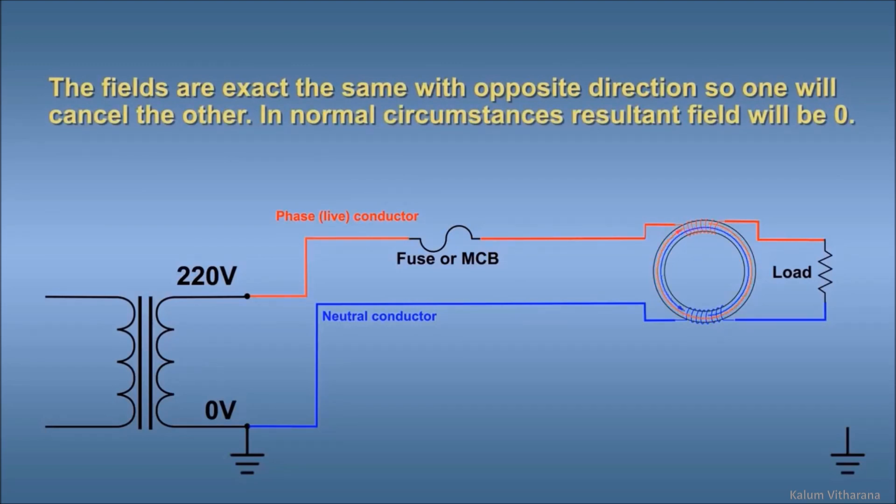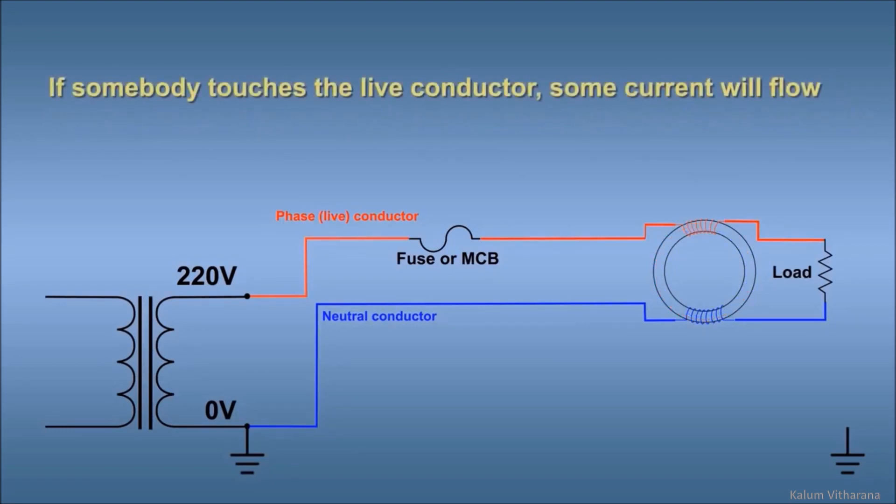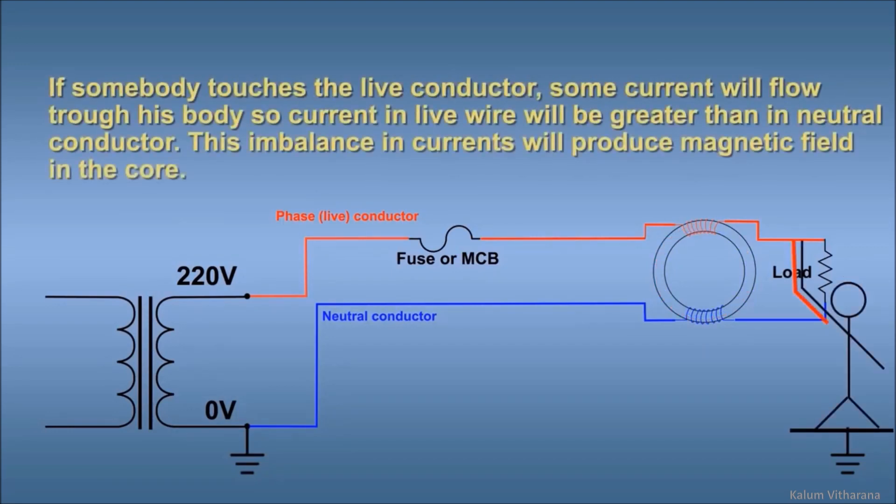The magnetic fields are exactly the same with opposite directions, so one will cancel the other. In normal circumstances, the resultant field will be zero. If somebody touches the live conductor, some current will flow through their body, so the current in the live wire will be greater than in the neutral conductor. This imbalance in currents will produce a magnetic field in the core.